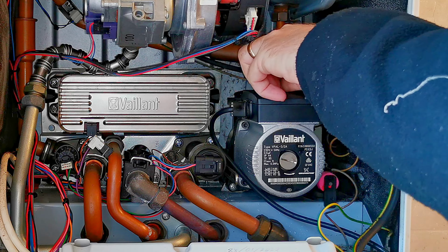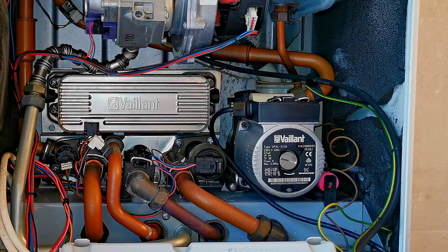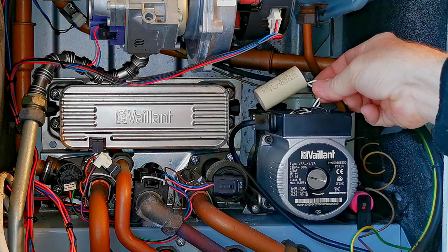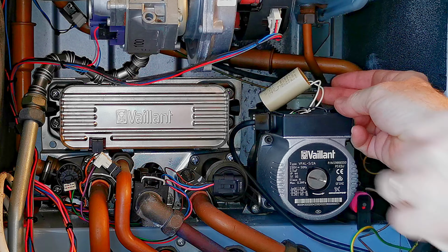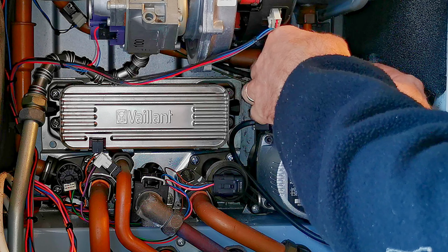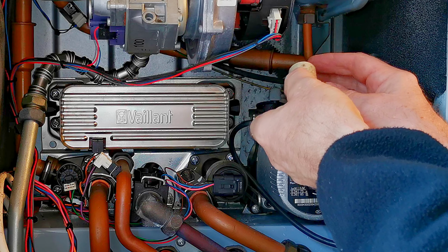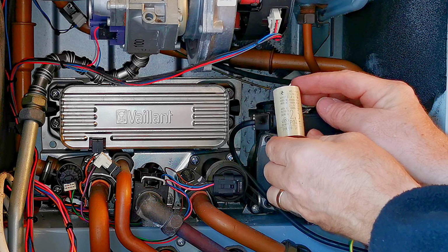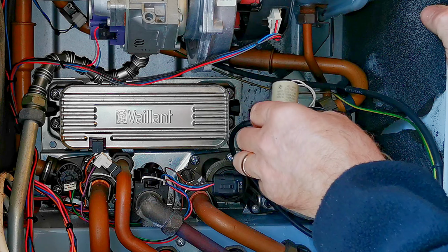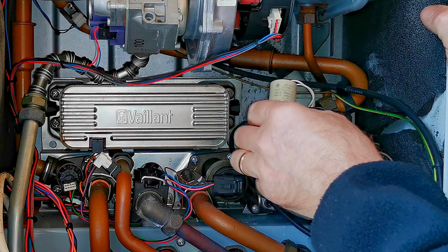Now there's one other thing that I would check before I go replacing the pump, and that's the capacitor in the pump. If that's faulty, then the pump will not run. A new capacitor is only around £10. So replacing the capacitor is way cheaper and a lot easier than replacing the whole pump. And of course I made a separate video all about how to check if a capacitor is faulty in a pump.